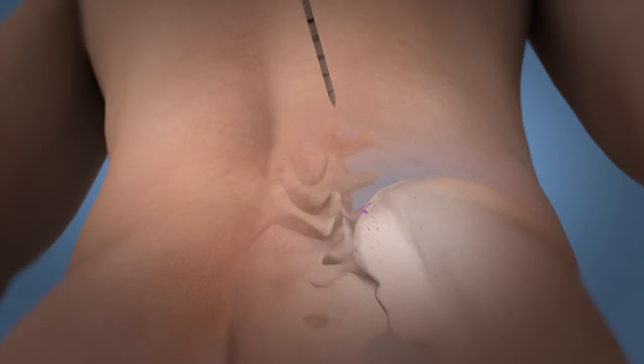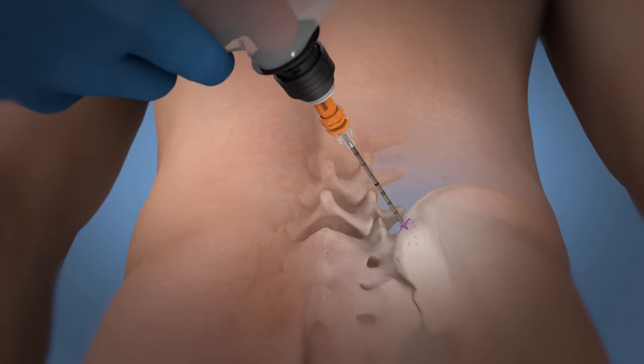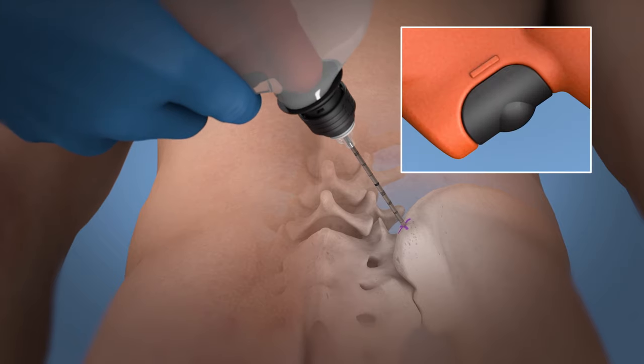Insert the needle manually through the patient's soft tissue to the periosteum at the desired location and angle. Gently attach the On-Control driver until an audible click is heard, which indicates attachment. Engage the driver trigger continuously with one to two pounds of downward pressure to penetrate the cortex.